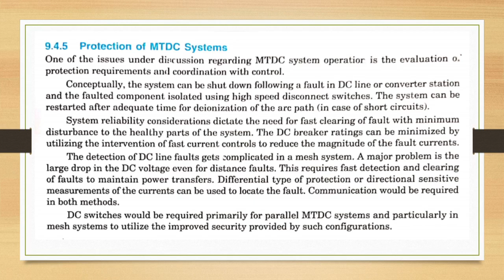The detection of DC line faults gets complicated in a mesh system. Major problem is the large drop in the DC voltage even for distant faults. This requires fast detection and clearing of faults to maintain power transfers. Differential type of protection or directional sensitive measurements of the currents can be used to locate the fault. Communication would be required in both the methods. DC switches would be required primarily for parallel MTDC systems and particularly in mesh systems to utilize the improved security provided by such configurations.